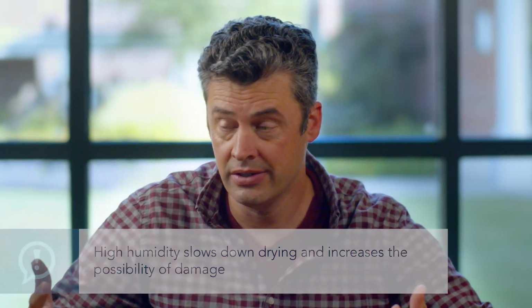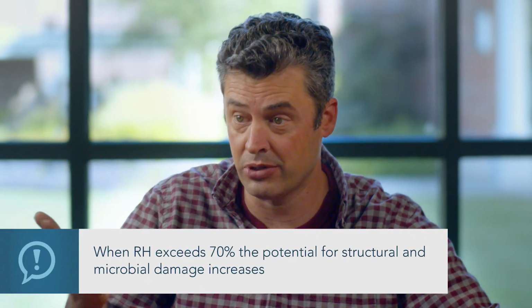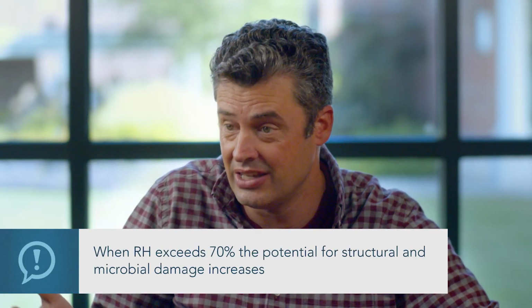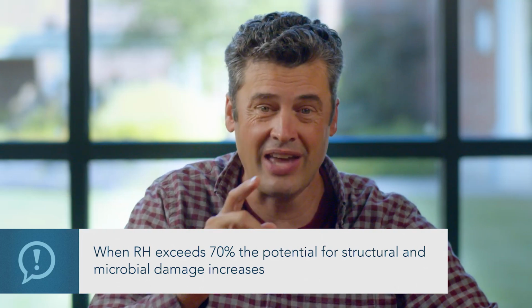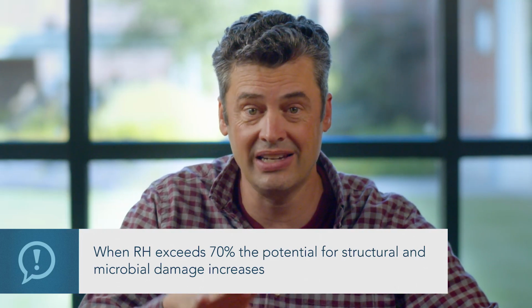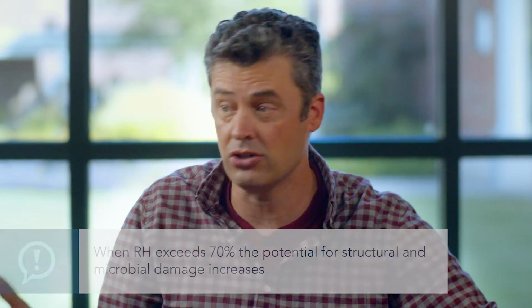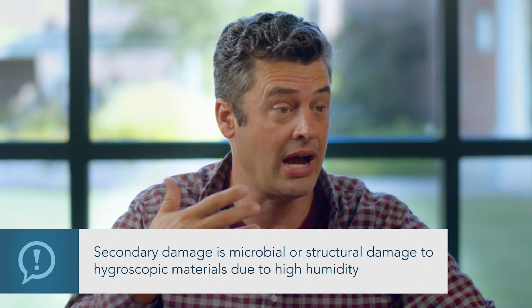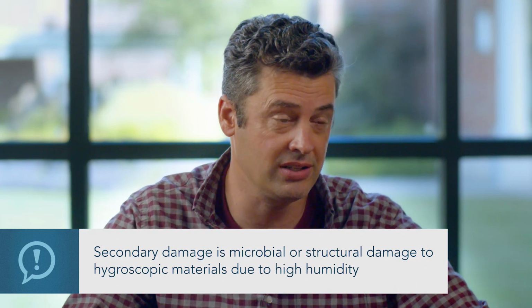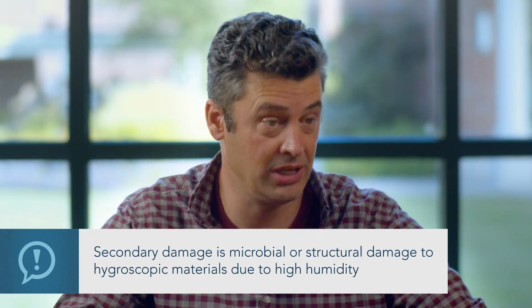And that's bad. It's also bad when the relative humidity of the environment exceeds 70%. So it's gotten too high. At that point, the potential for secondary damage or microbial damage goes way up, and you're definitely in a situation where the conditions are ideal for secondary damage. Now, what's secondary damage? Secondary damage is damage to hygroscopic building materials or contents because of high humidity.